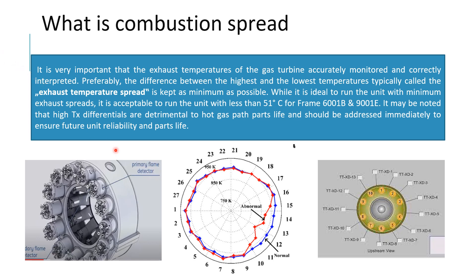In this image you can see that temperature elements are located on the exhaust side, measuring temperature at each point around the turbine. The green-blue line and the red line indicate different temperature distributions. In the blue line, the temperature is more or less uniformly distributed — that is a healthy condition. But in the red line, the temperature at some places is around 950 degrees Kelvin and very low at others, showing a problem in the combustion process.